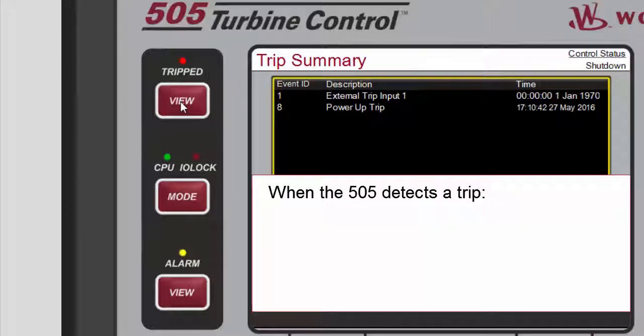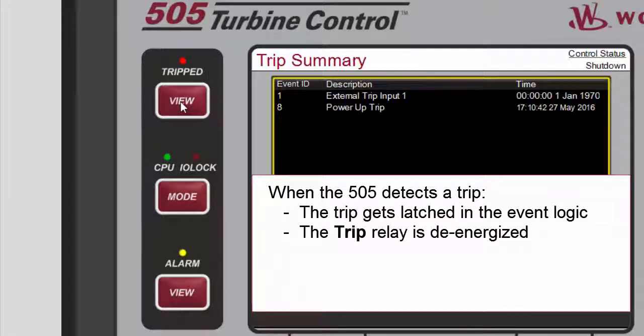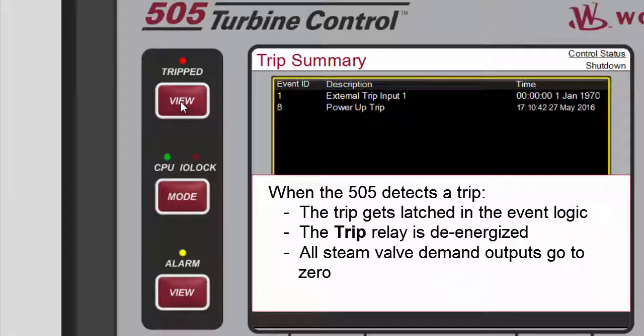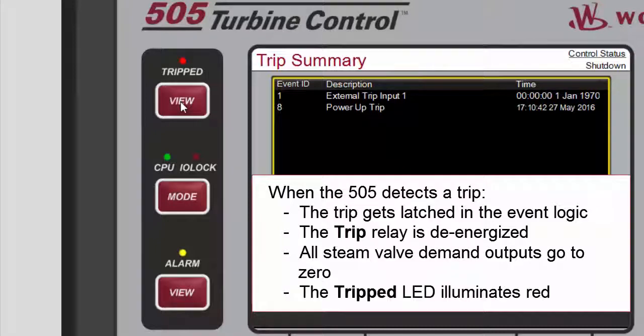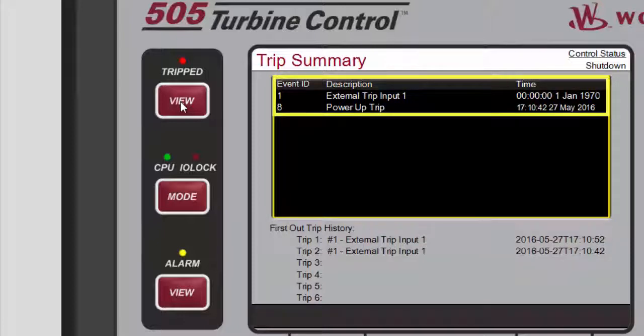When a trip is detected, it gets latched in the event logic. The trip relay is de-energized. All steam valve demand outputs go to zero, and the Tripped LED illuminates red. The cause of the event will be indicated with an event ID, description, and time and date stamp.